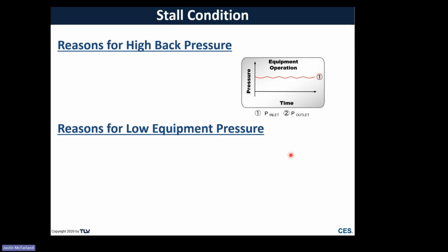So big question in everybody's mind now is, well, why would you have high back pressure? Okay, I understand that that's a bad thing, Justin, but why would anybody have that? Well, could be that just the condensate system pressure itself is high. Doesn't necessarily mean that it was designed that way, but there could be a lot of other issues going on in a plant. Could be that there's leaking steam traps, could be that there's open bypass valves, could be that there's different equipment or units that have been added on over time and trying to put more and more condensate into the condensate return system that's never been upgraded. And over time with all those things, then that can cause a slow or even potentially dramatic increase in condensate return pressure.